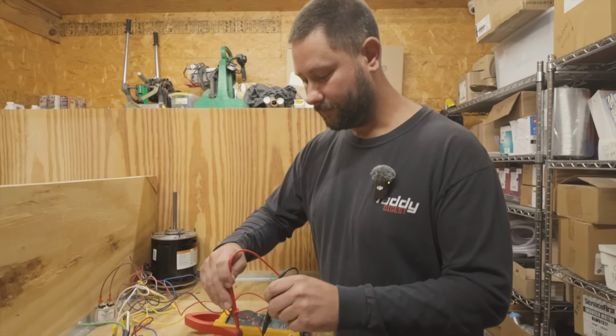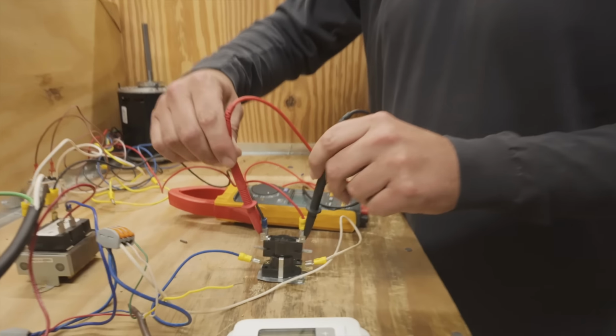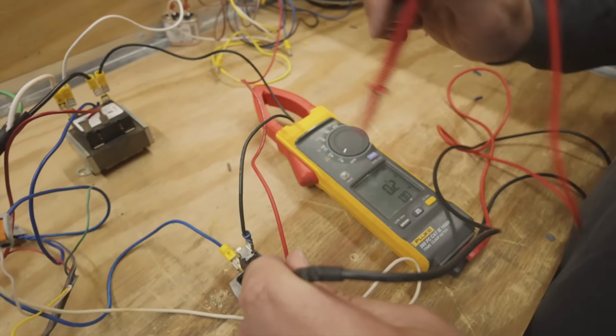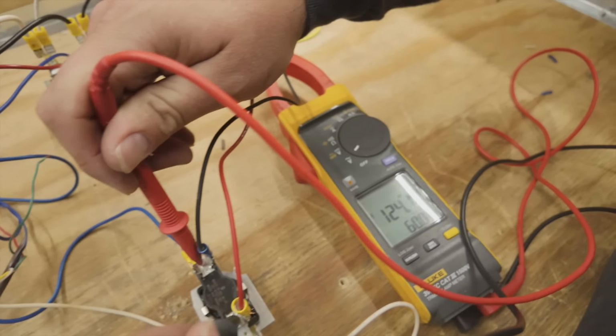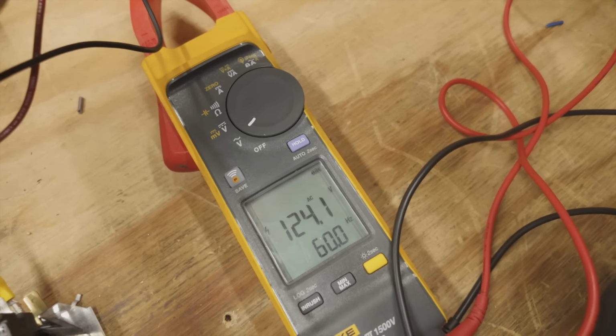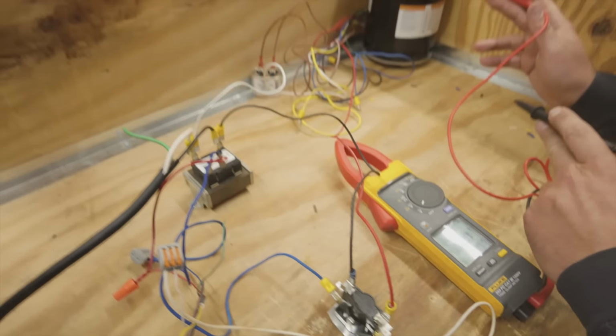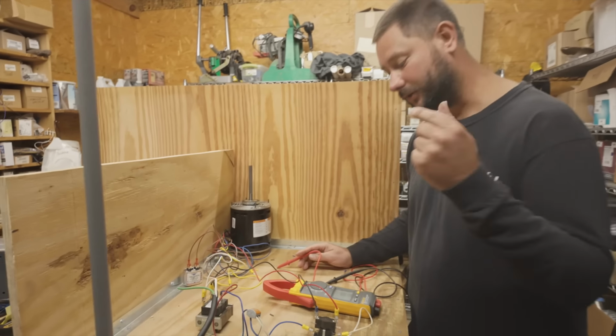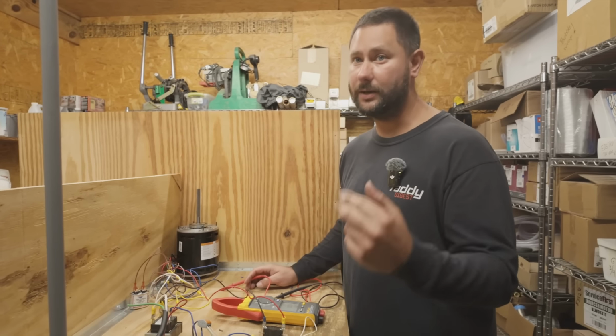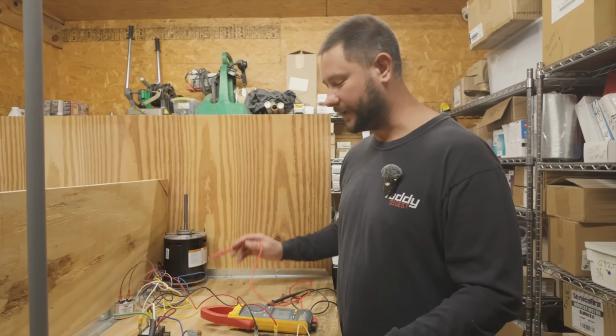Circuit's not complete. But if we check across, I should have said that earlier, I should have been more specific with that. Checking across, we got 120. But there's no power going to our motor. But what's it going to read whenever it closes? It's going to read 0, right? We've completed the circuit, our fan's going to kick on.